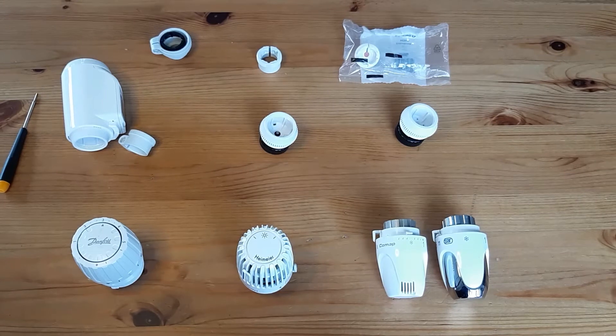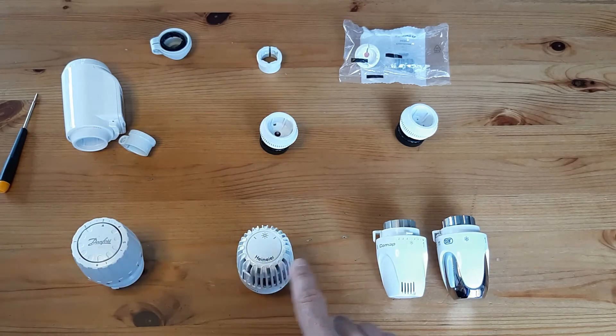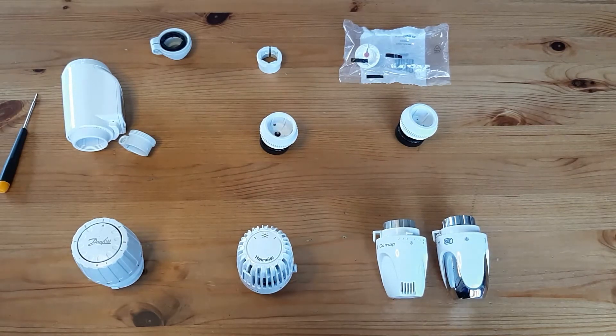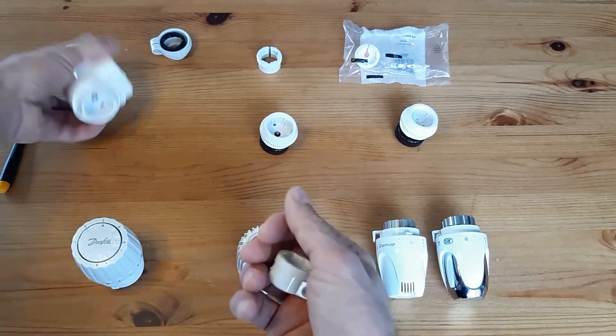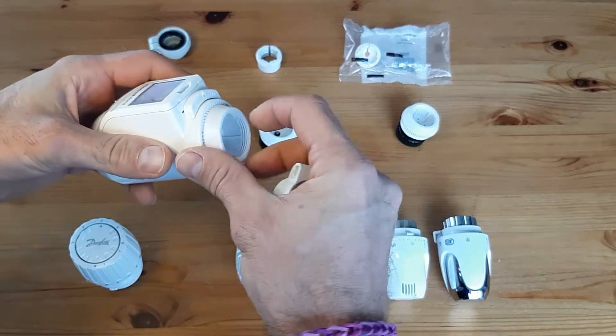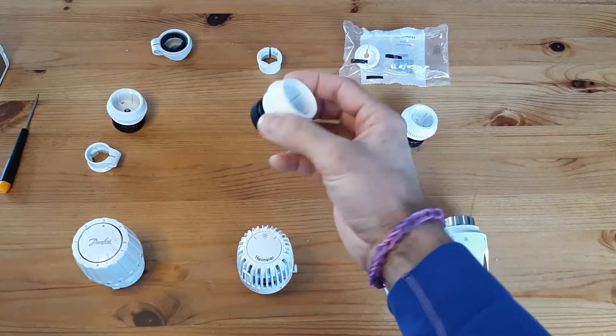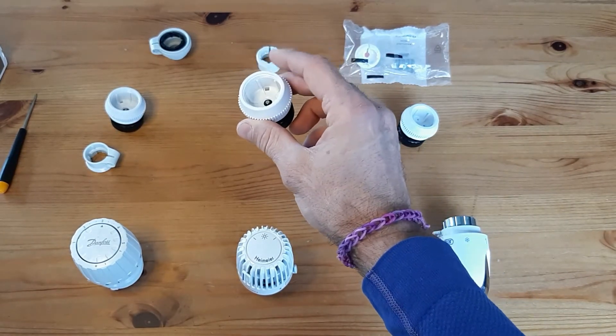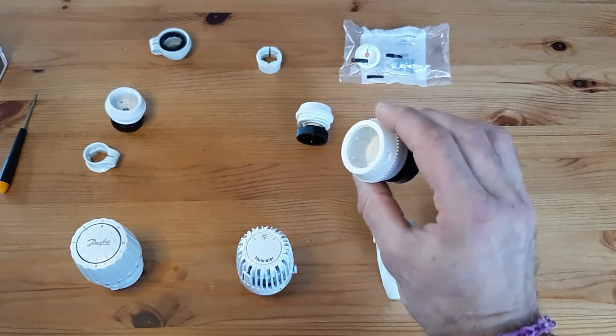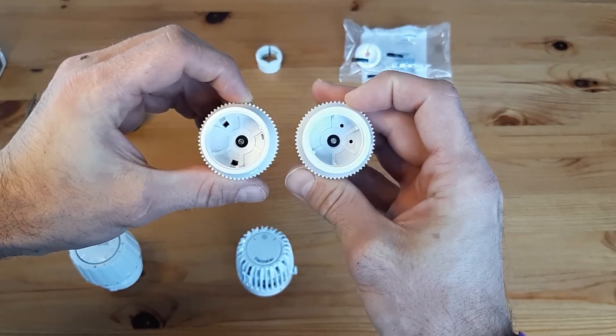Hello guys, I promised you another video on how to install the radiator controller HR 92 from Honeywell. We will install it for different thermostatic heads: Danfoss, Heimeier, and Comap. For Danfoss you need a special adapter which then gets screwed onto the Honeywell adapter. For Heimeier it's very easy — this adapter is already from Honeywell, you just literally screw it on. The same goes for Comap; they are only different in sizes, otherwise it's just a screw-on.